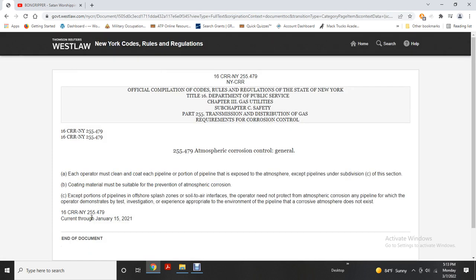Atmospheric corrosion control — general: each operator must clean and coat each portion of the pipeline that is exposed to the atmosphere, except as provided under subdivision C. The coating must be suitable for preventing atmospheric corrosion. Except for portions of the pipeline at offshore splash zones or soil-air interfaces, an operator need not protect against atmospheric corrosion for any pipeline where the operator can demonstrate through testing or investigation and experience that a corrosive atmosphere does not exist.